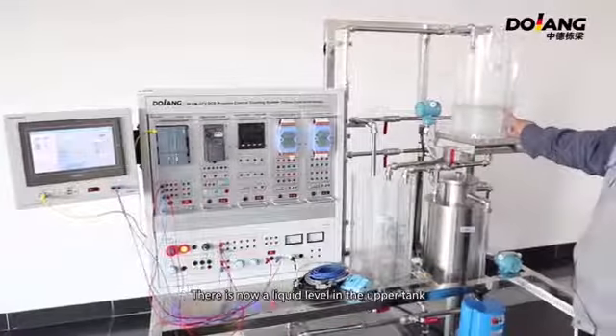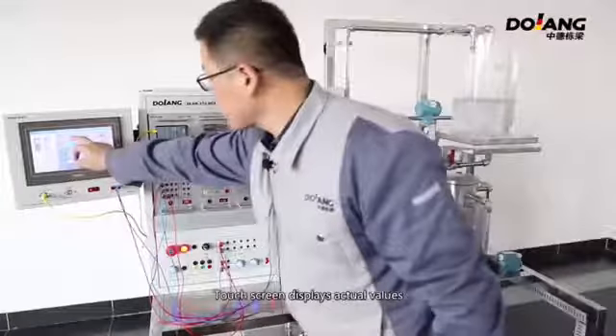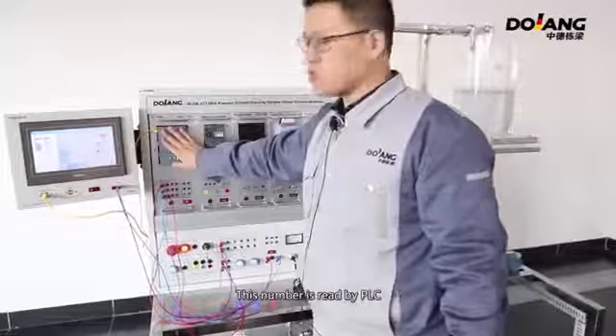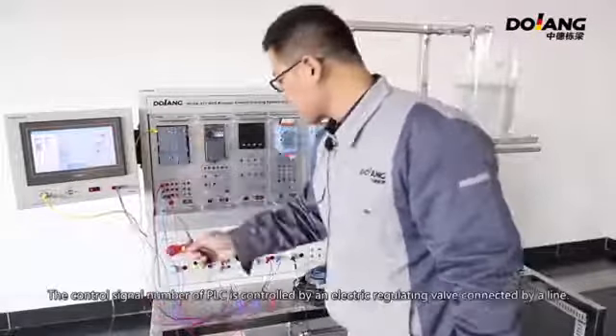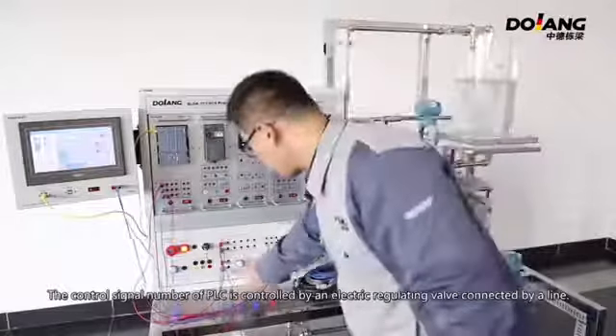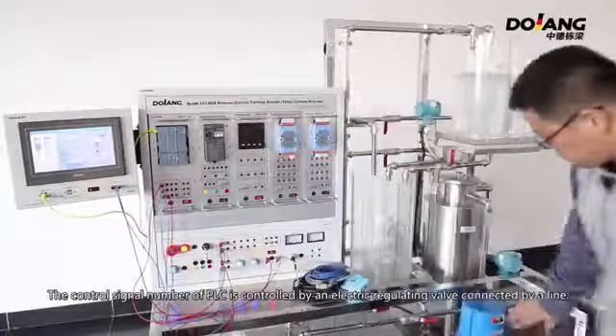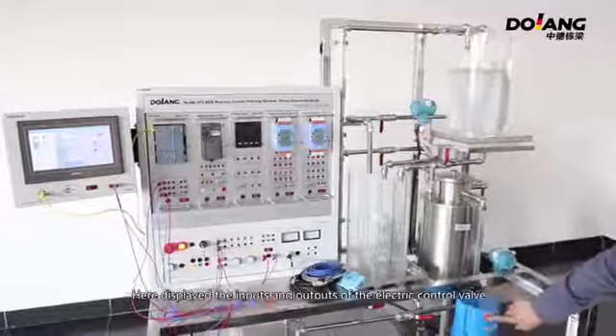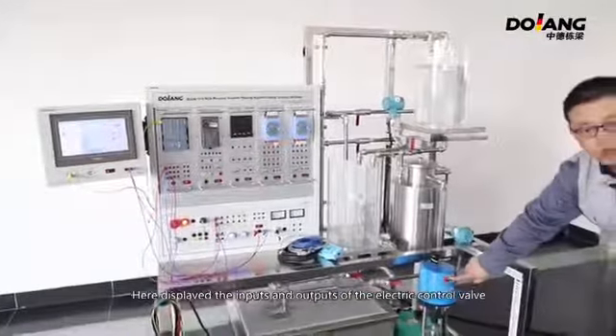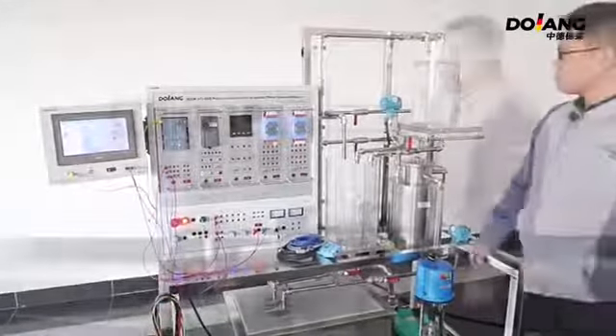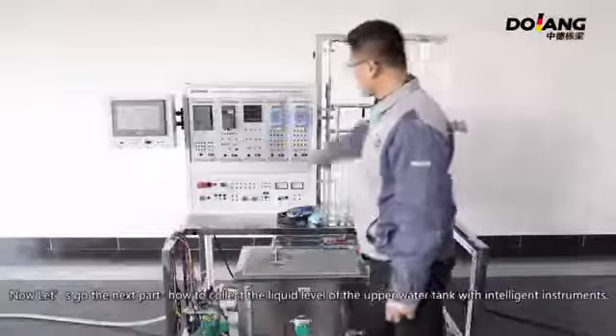There is now a liquid level in the upper tank. The touch screen displays actual values. The number is read by PLC. The control signal number of PLC is controlled by an electric regulating valve connected by a line. Here display the inputs and outputs of the electric control valve.